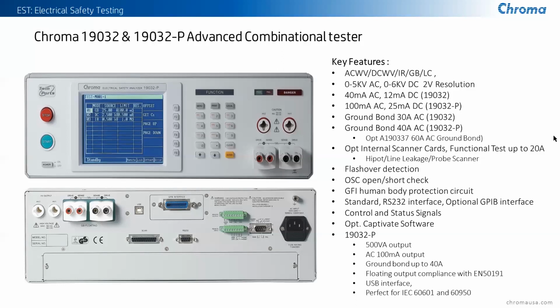So we also offer with this one the ability to have optional interface scanner, internal scanner cards. What these are for is, they have the various types of relay connections to simulate the faults that we discussed earlier for open and various types of fault conditions, like switching the line and the neutral, or opening the ground wire or the neutral wire during the test to see if it has an adverse effect on leakage current. It includes the flashover detection. It also has the open and short circuit check, and it also includes the testing for various types of control signals.